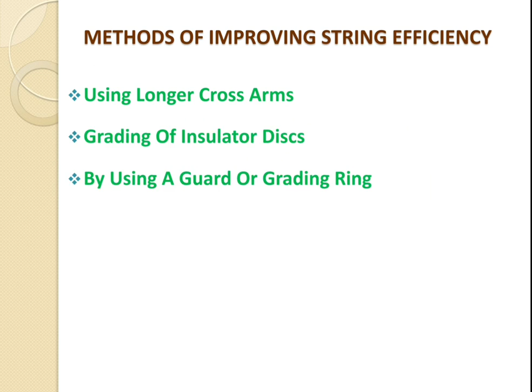And the third one is using a guard ring. The figure shows a grading ring, which can be used for improving the string efficiency. The potential across each unit in the string can be equalized by using a guard ring, which is a kind of metal ring provided nearer to the conductor, surrounding the metal fittings and the line conductor.